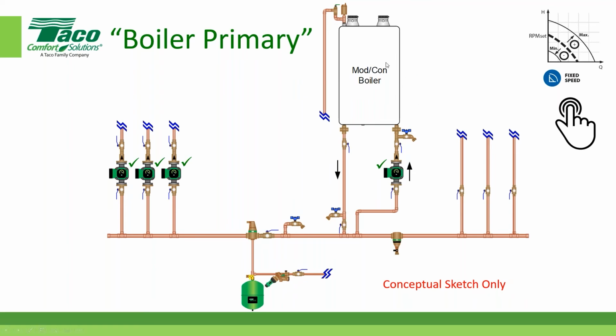If this manufacturer allowed you to go out to, let's say, a 35 or maybe a 40, let's do that same calculation again. 155,000 divided by 40 divided by 490. I only need 8 gallons a minute for a 155,000 BTU boiler. And that's only if I need to deliver 155,000 BTUs. Many times the boiler is bigger than you actually need because you guys as wholesalers didn't have one that was only 138,000, so you gave them a 155. That never happens. Of course, it happens all the time.